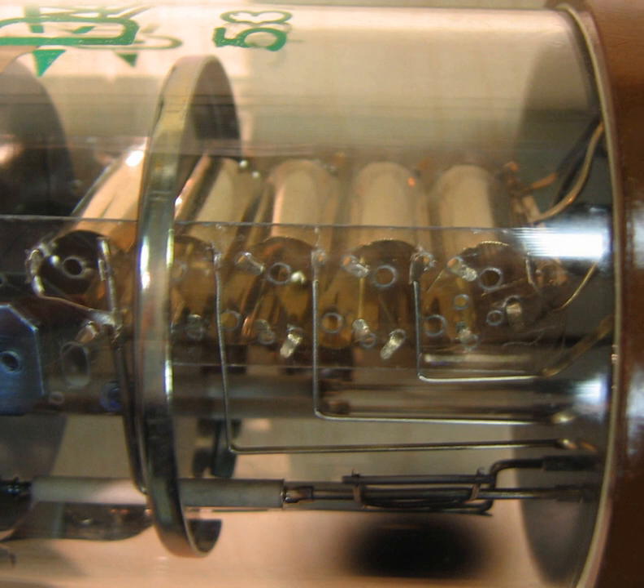Window materials: The windows of the photomultipliers act as wavelength filters, this may be irrelevant if the cutoff wavelengths are outside of the application range or outside of the photocathode sensitivity range, but special care has to be taken for uncommon wavelengths. Borosilicate glass is commonly used for near-infrared to about 300 nanometers. High borate borosilicate glasses exist also in high UV transmission versions with high transmission also at 254 nanometers. Glass with very low content of potassium can be used with bialkali photocathodes to lower the background radiation from the potassium-40 isotope. Ultraviolet glass transmits visible and ultraviolet down to 185 nanometers. Used in spectroscopy.